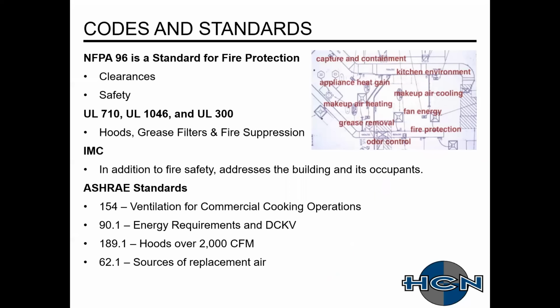So as designers and installers, when you get a commercial kitchen ventilation system, a lot of people push it off to the side for the kitchen consultants or equipment providers. Typically you'll have two different kinds of design: whatever the kitchen guy does, and then on the MEP side, what you guys do for the rest of that design. The codes and standards that dictate kitchen ventilation systems: NFPA 96 is the cap.